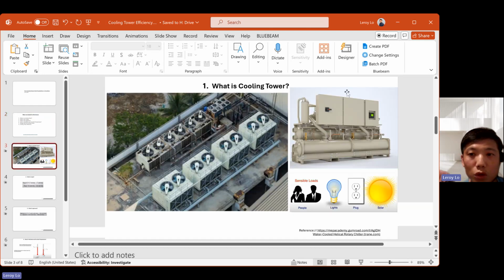Okay. So what is a cooling tower? Moving on to this one. You can see on the left side the photo. Cooling towers are used to remove heat from water in water-cooled applications in industry. This usually means removing the heat from water-cooled chillers. You can see a photo of a water-cooled chiller on the top right, and the water-cooled chiller usually takes the heat from the buildings. You can see the common heat sources at the bottom right of the photos.